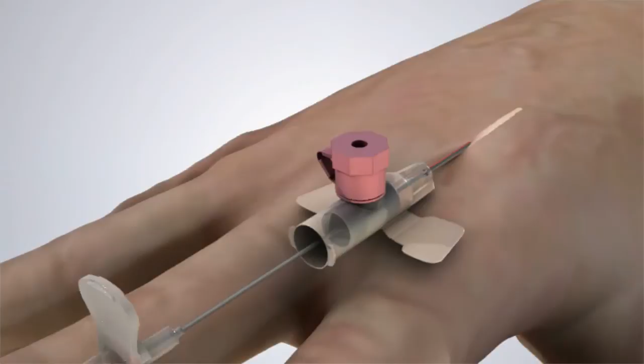Nipro WingCath is sterilized using Nipro's in-house gamma sterilization technology. Sterilization is critical to every medical device. It is a process that effectively eliminates almost all microorganisms like bacteria, viruses and fungi from the medical device and makes it safe for the patients. We at Nipro have adopted the Gen Next sterilization for our medical devices. Gamma radiation, which is fast becoming the most popular new technology across the globe to improve the shortcomings of various other methods of sterilization. Nipro has been accorded approval from the Atomic Energy Regulatory Board of India to introduce in India in-house gamma technology for sterilizing devices.